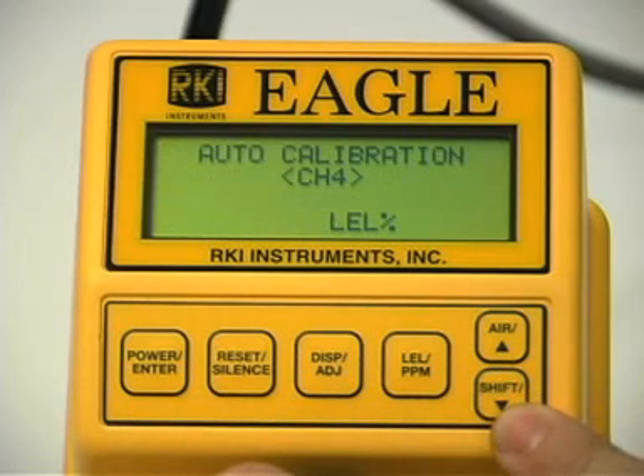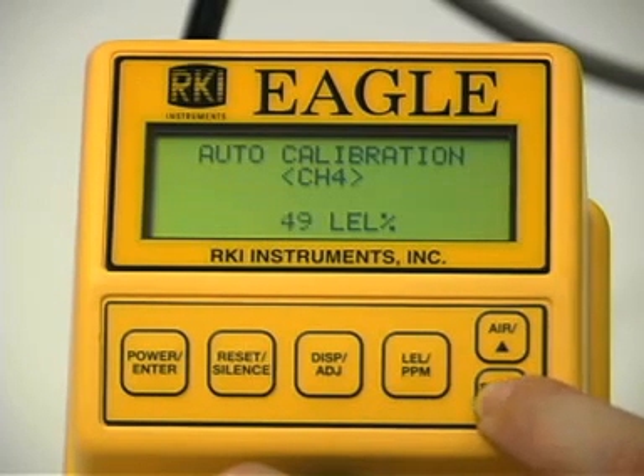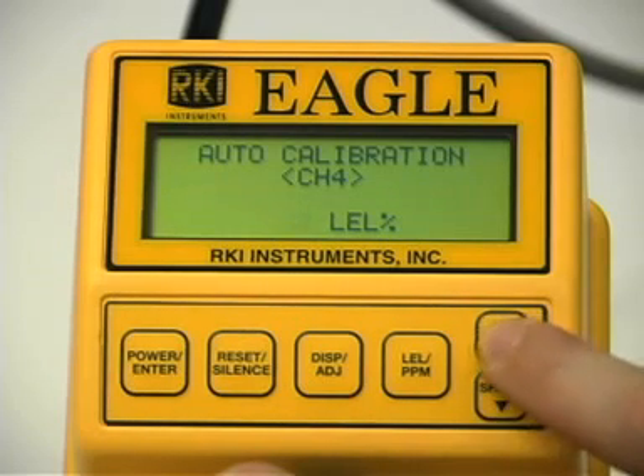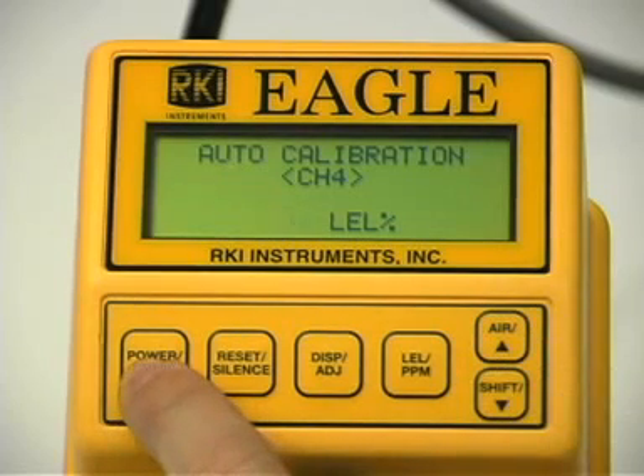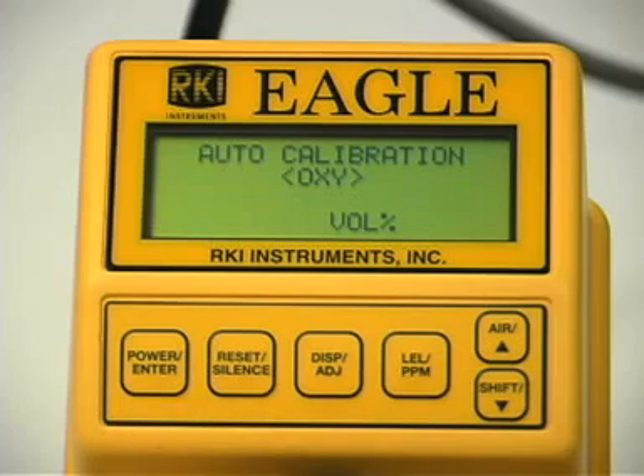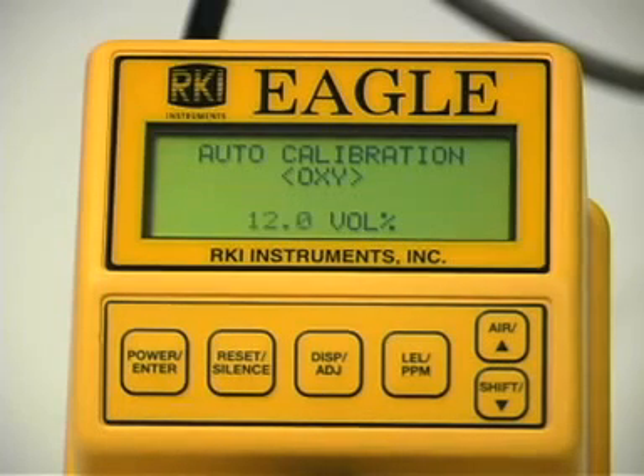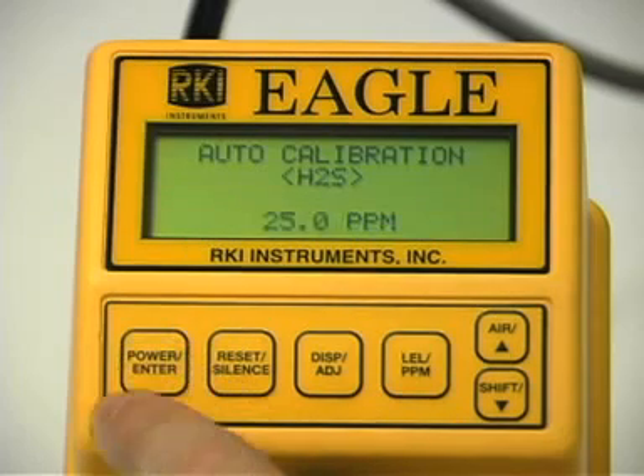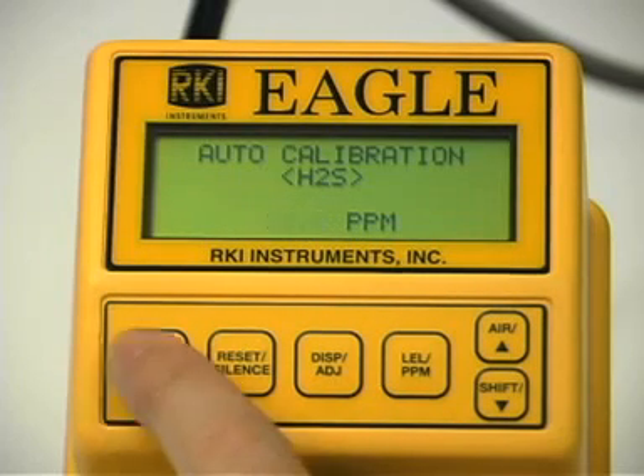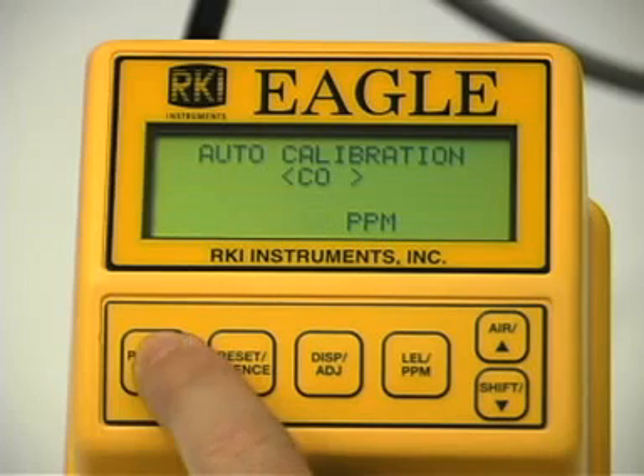The auto-calibration screen for the combustible gas channel displays. Use the up and down buttons to set the correct combustible gas value. Press the enter button to save the new setting. The auto-calibration screen for the next channel displays. Repeat this procedure to set the correct values for the remaining channels and return to the calibration values screen.